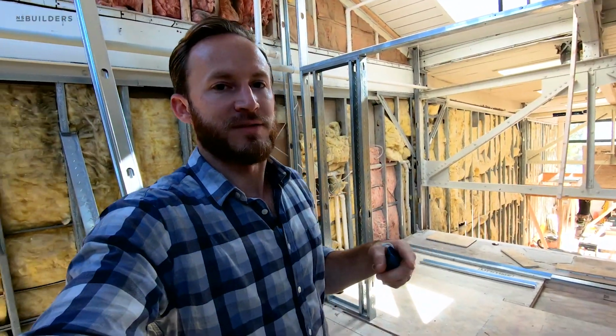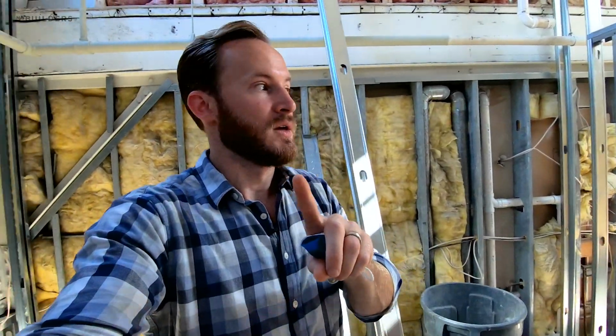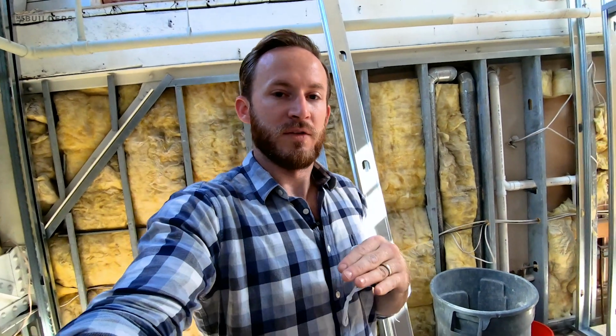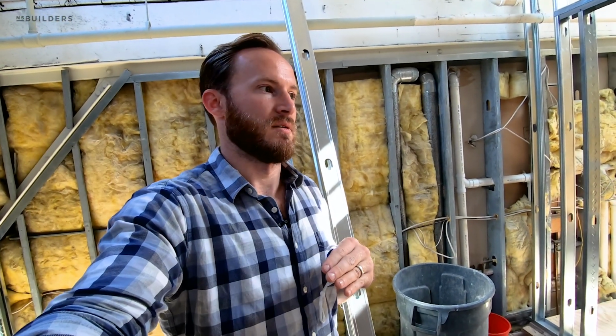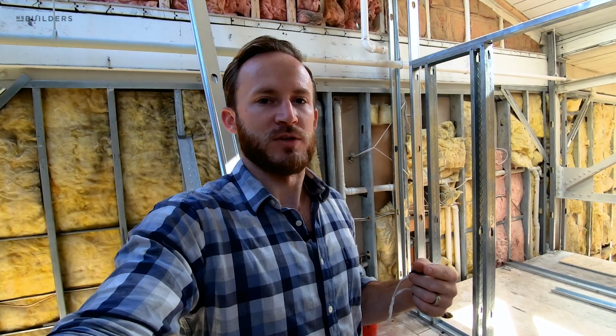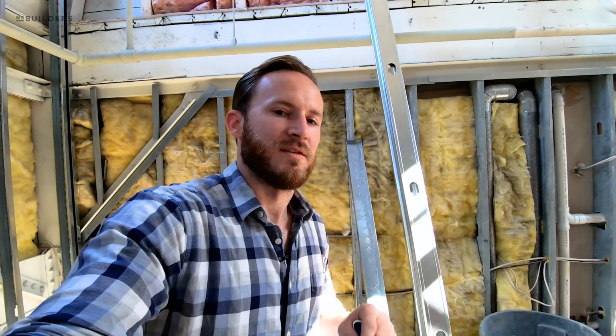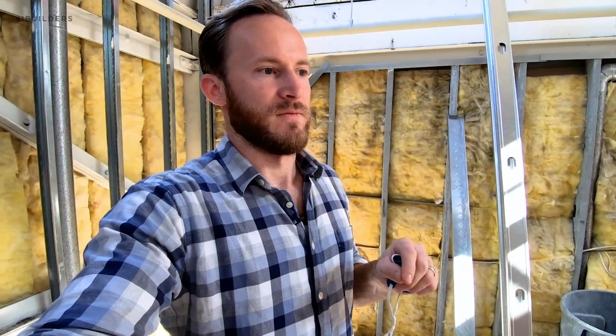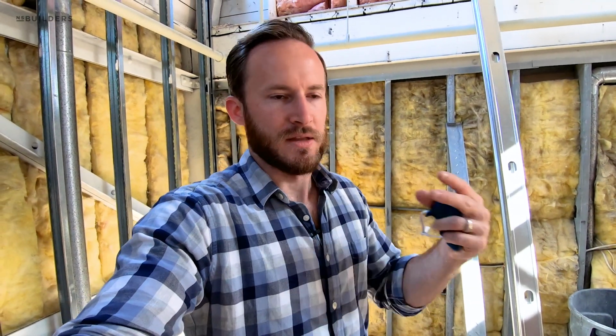We're working with Ross at T2 Engineering, along with our HVAC contractor, to work through these details. One thing I forgot: we're installing a low CFM kitchen exhaust, so we're not bringing in makeup air, but we are installing a high CFM ERV to help combat the radon issue we discussed earlier in this project, plus ultrafiltration. All the air handlers will have MERV 13 filters, and so will the ERV. We're also investigating UV light filtration for viruses and things like that.